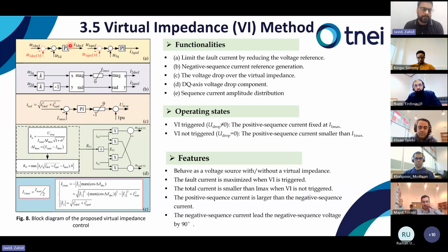You can see the block diagram on the left hand side in figure 8, and these are the functionalities of these blocks. For example, this block is used to limit the fault current by reducing the voltage reference, and this block is used for negative sequence current reference generation, then the voltage drop over the virtual impedance, the DQ-axis voltage drop component, and finally the sequence current amplitude using the virtual impedance calculation.